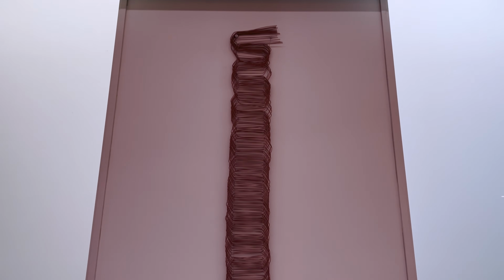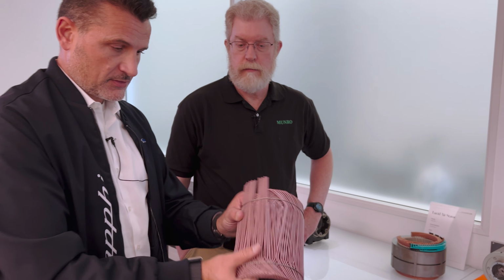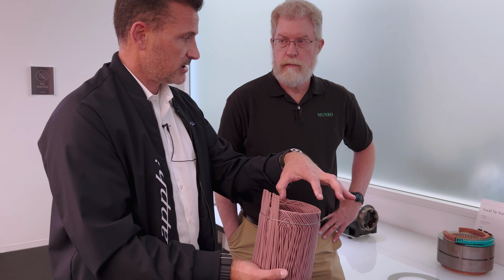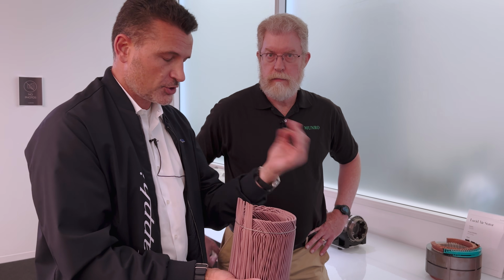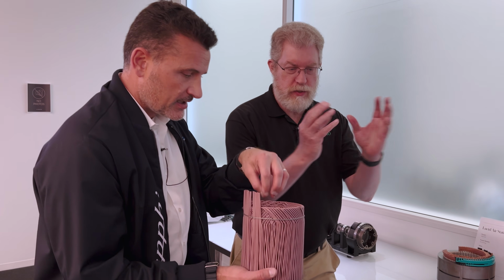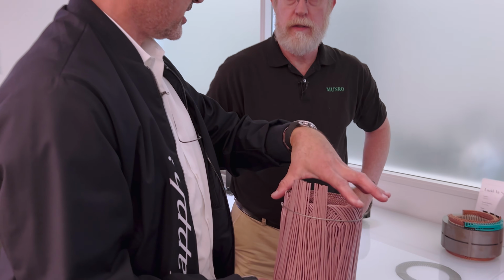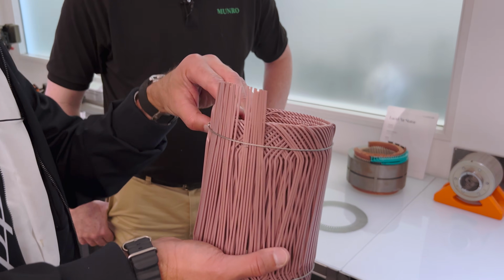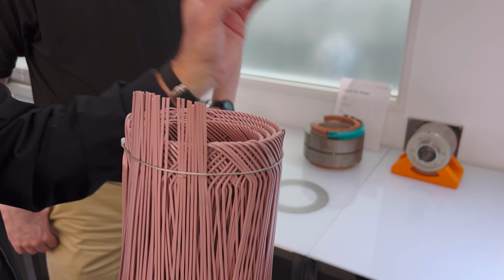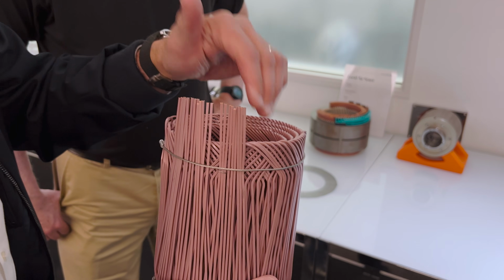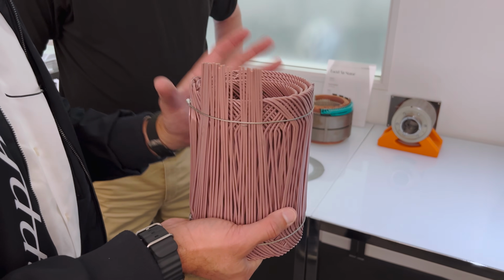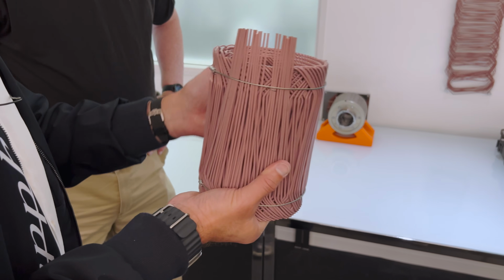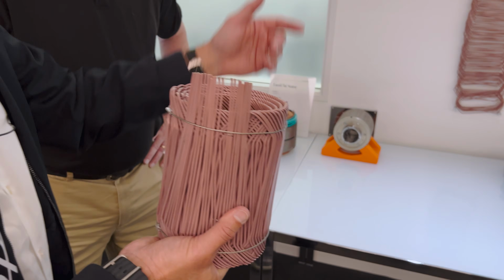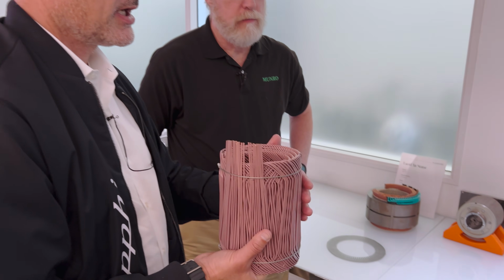It's literally like on a loom. It gets wound up on a blade, then rolled up, and inserted into the stator in one shot, radially. It radially gets pushed in, and then the end winding gets bent over slightly to keep it in place. Then we put in the slot liners on the inside. It's a super efficient process - the winding, the rolling, and the insertion are all fully automated.